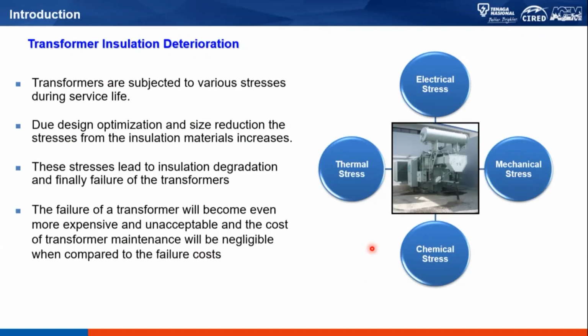So when we talk about stresses, we are talking about electrical stress, mechanical stress, chemical stress, as well as thermal stress. And furthermore, nowadays, due to optimization of materials, the size of the transformer is reduced. And because of that, the stress experienced by the transformer has increased. So the failure of a transformer will become even more expensive and quite unacceptable as compared to the cost to make sure that the transformer is in good shape.